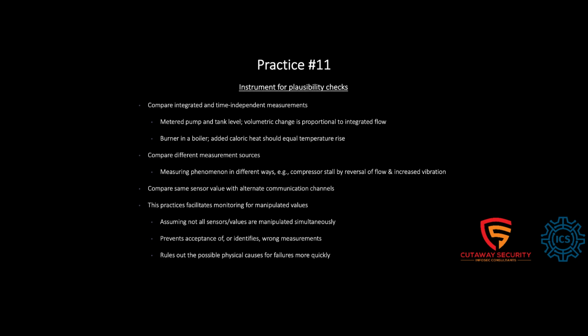So if you see the tank level increasing, but there is no flow increase, or vice versa, something is wrong. Similarly, if you have a boiler, the added caloric heat in the boiler should be proportional to the temperature increase. If they're not, if someone is trying to manipulate those values, you can create an alert to say these two things should be proportional, and they're not. It could point to a simple equipment failure, a flow meter problem or a level indicator problem, or it could be that someone is manipulating those values. But this kind of practice will help you create an alert for it, so you can go take a look and see that these two things that are supposedly connected have diverged at this moment.